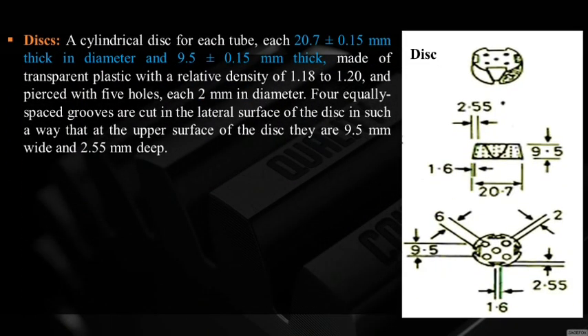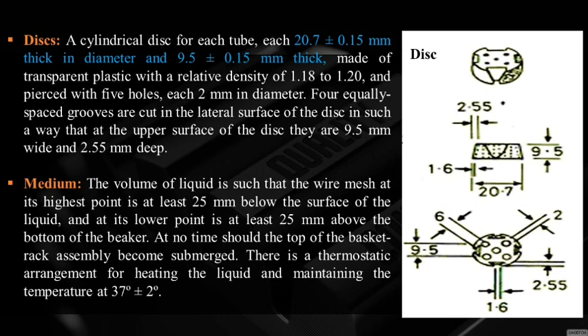A cylindrical disc is used for each tube — 20.7 ± 0.15 mm in diameter and 9.5 ± 0.15 mm thick, made of transparent plastic with a relative density of 1.18 to 1.20, pierced with 5 holes each of 2 mm. Four equally spaced grooves are cut in the lateral surface of the disc. The volume of liquid is such that the wire mesh at its highest point is at least 25 mm below the surface of the liquid when the basket is at its highest point.